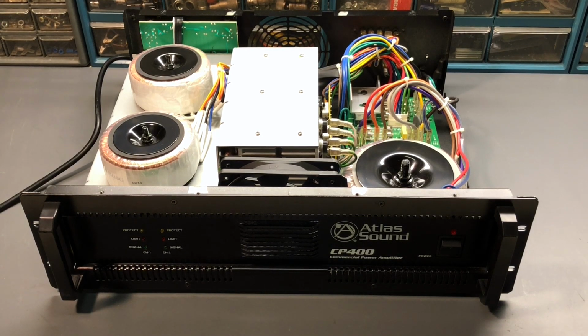Knowing what it can protect against, the DC offset is something I would look at first, and we'll try to take a measurement and see if that's actually occurring. Maybe it has a DC offset from a failed output device or some other part of the circuitry that isn't working right.